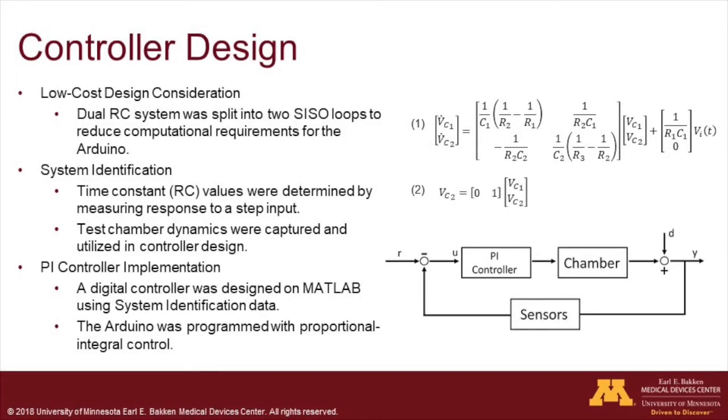After these steps were taken, a feedback controller was designed to simulate the pressure profile experienced in the human body. Since a single RC circuit is a simple single input, single output system, the serial RC system was split into two loops to optimize Arduino computation.